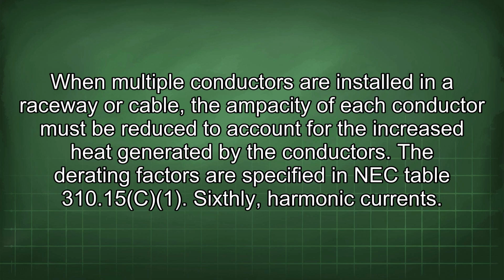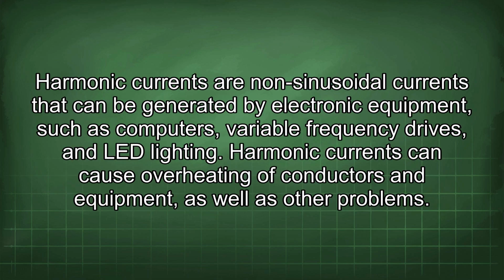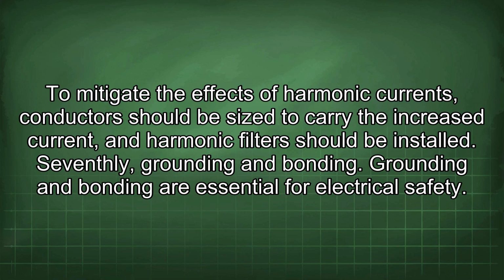Sixthly, harmonic currents. Harmonic currents are non-sinusoidal currents that can be generated by electronic equipment such as computers, variable frequency drives, and LED lighting. Harmonic currents can cause overheating of conductors and equipment, as well as other problems. To mitigate the effects of harmonic currents, conductors should be sized to carry the increased current, and harmonic filters should be installed. Seventhly, grounding and bonding.